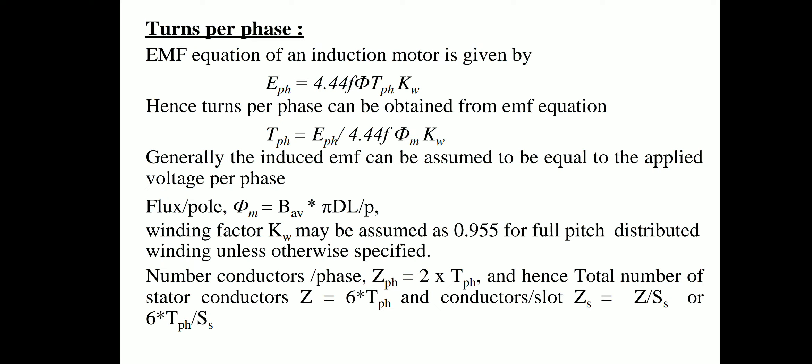The EMF equation of an induction motor is: Eph = 4.44 × f × φ × Tph × Kw. Hence turns per phase: Tph = Eph / (4.44 × f × φm × Kw). The induced EMF can be assumed equal to the applied voltage per phase. Flux per pole: φm = Bav × πDL / p. The winding factor Kw may be assumed as 0.955 for full pitch distributed winding unless otherwise specified.